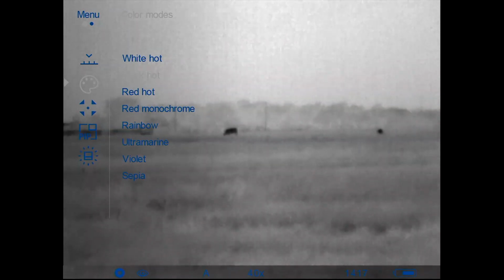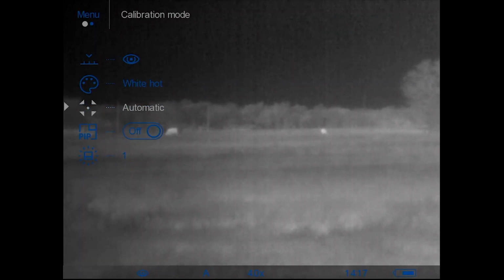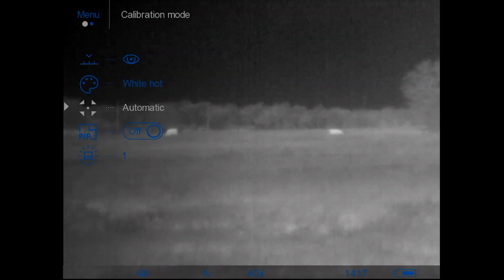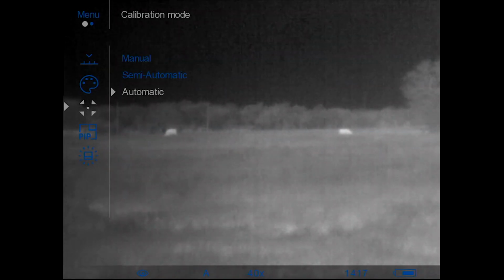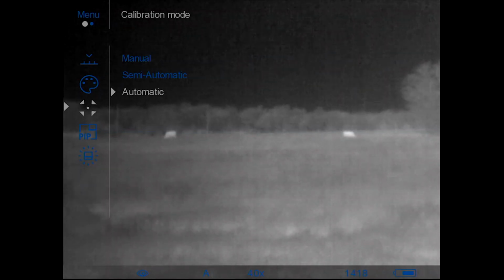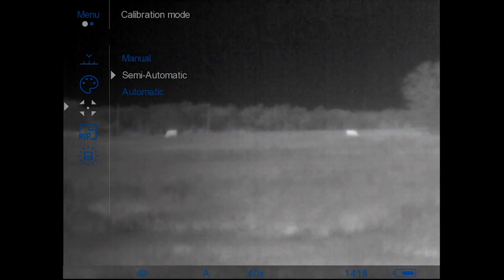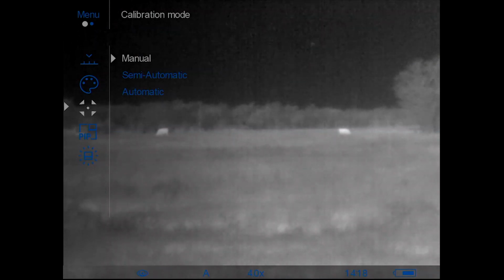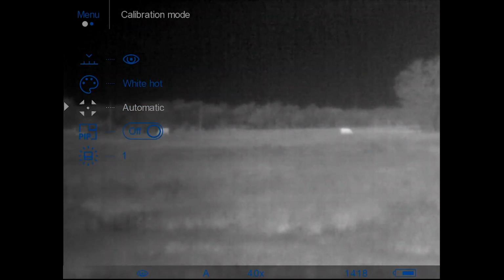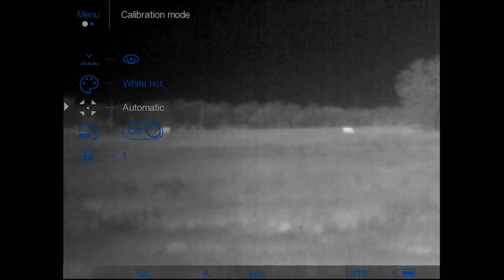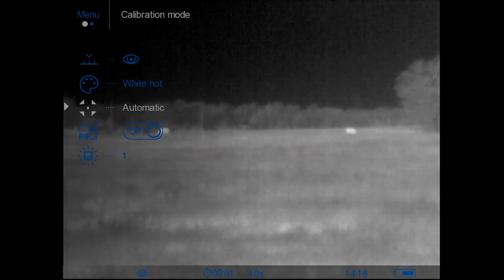Everybody has their own. The next selection in the menu is calibration mode. All thermals have 3 different calibration modes, which is automatic, semi-automatic, and manual. If I leave mine in manual, I'll forget to do it sometimes, and the image will start to deteriorate. So I just leave it in automatic all the time. It's nice leaving it in automatic on this device because it allows you to manually calibrate while it's on automatic, and it will delay the next automatic calibration, which is really nice.